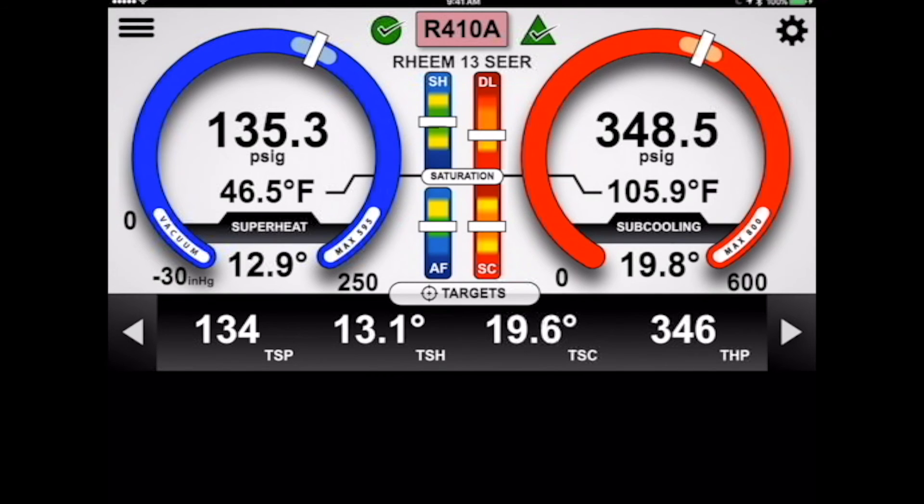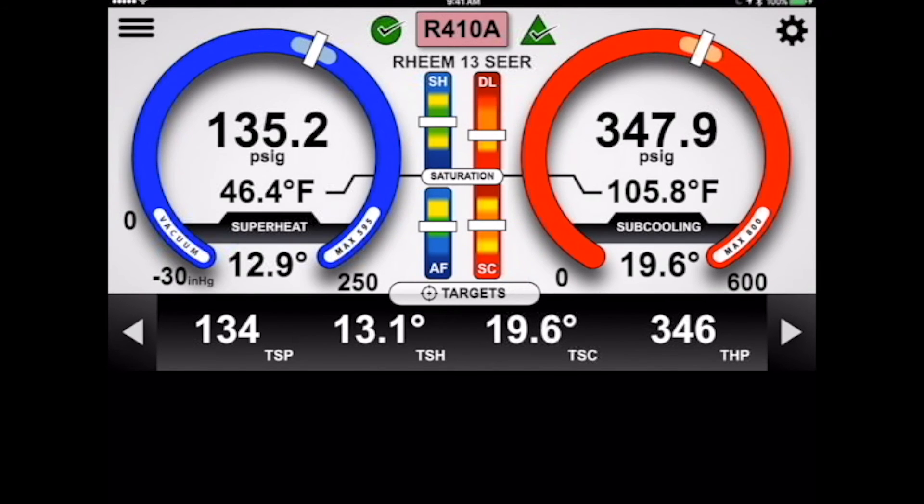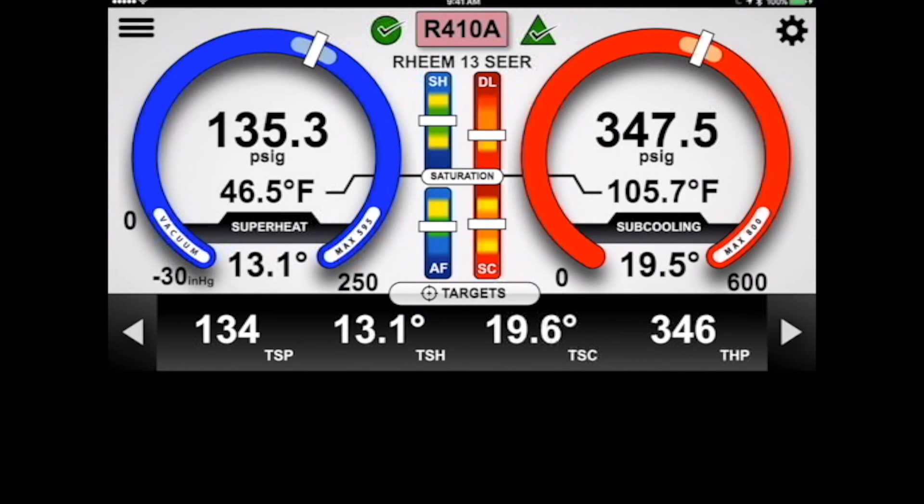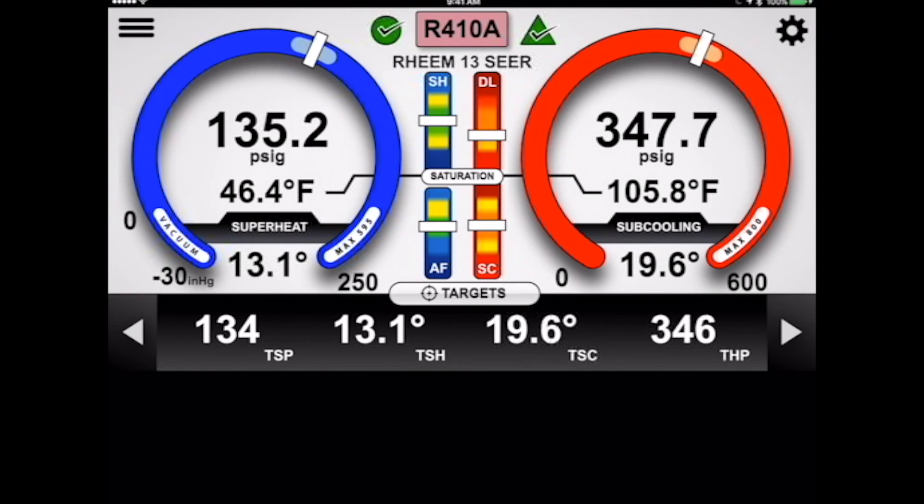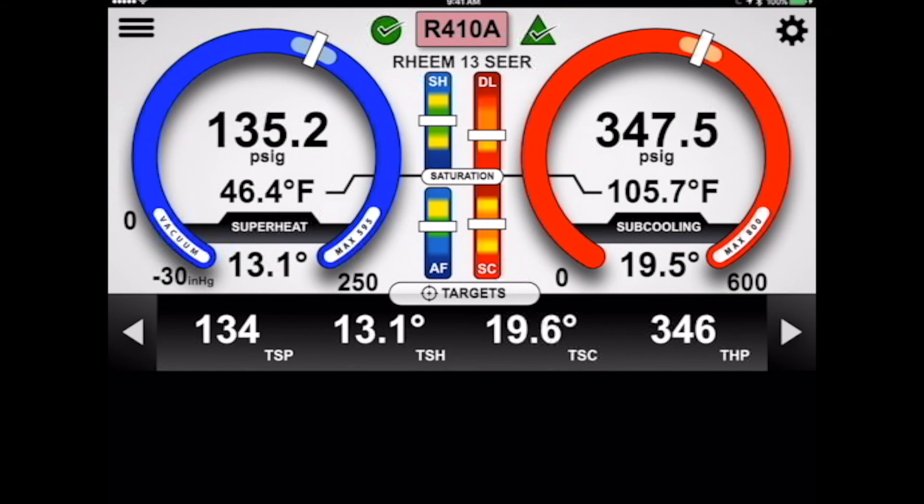Our pressures are dead center. We're at 134 target suction, we're at 135, 346, 348. Those are more or less spot on. You can't get too much more precise than that. Everything is set up by saturation temperature. So this system now has been benchmarked, and what we've just said is this is exactly the way that I want this piece of equipment to operate. We've baselined it for anybody at our company.